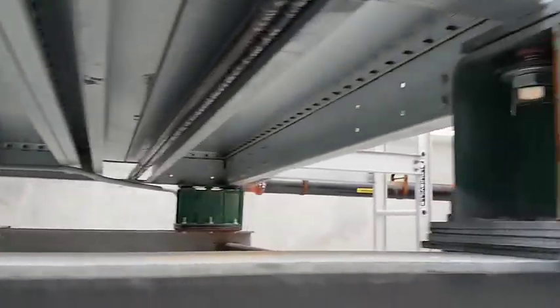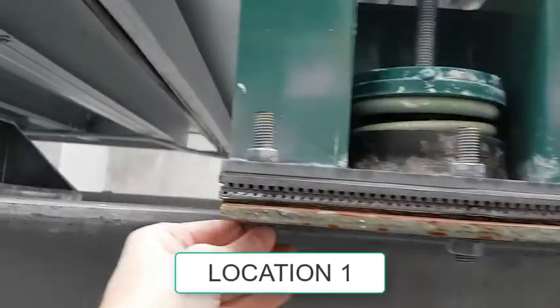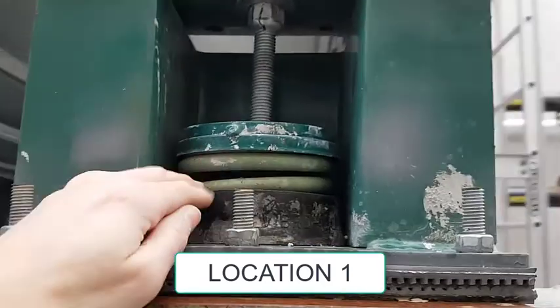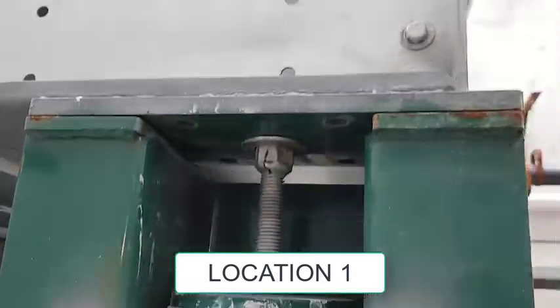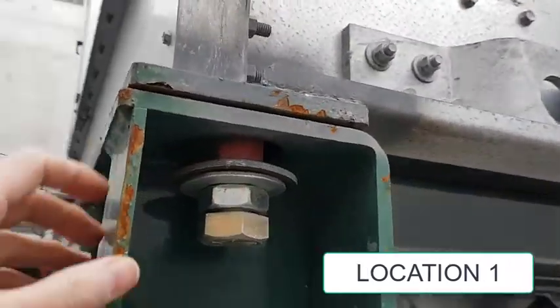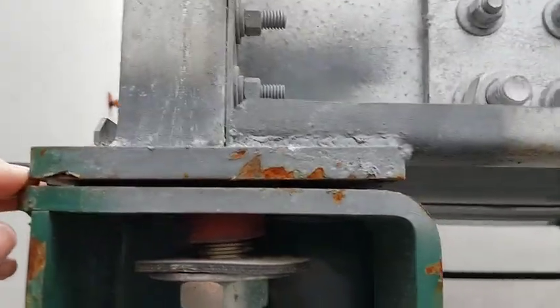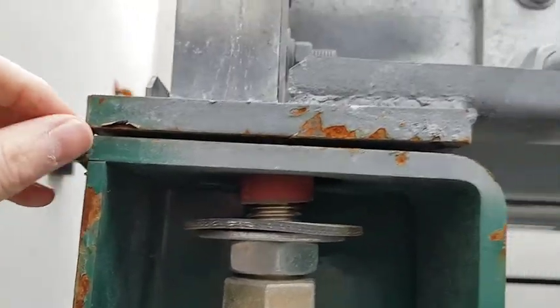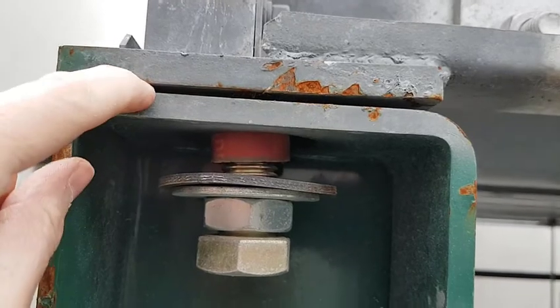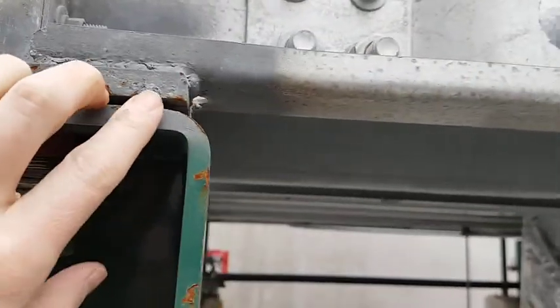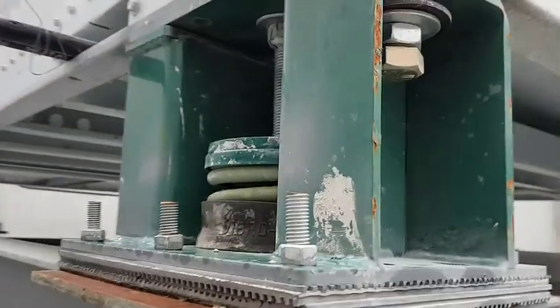And finally, we come to location 1, where we see the most compressed spring of the group, and the only location where the top plate is sitting on the side stanchions. This is evidence of installation instructions not being adequately followed. Note that the spacers have been removed, which means that the isolator was adjusted prior to the tower being filled with water. Though not impossible, this is difficult to fix.